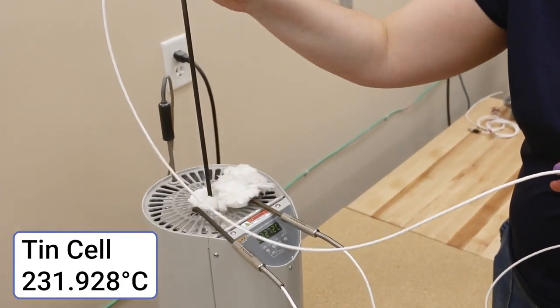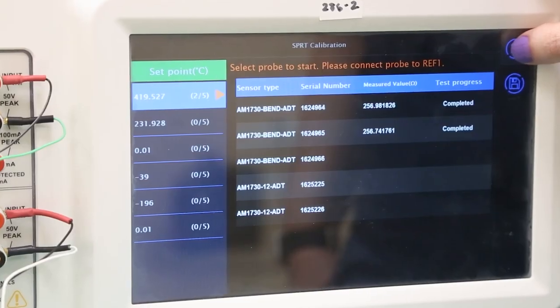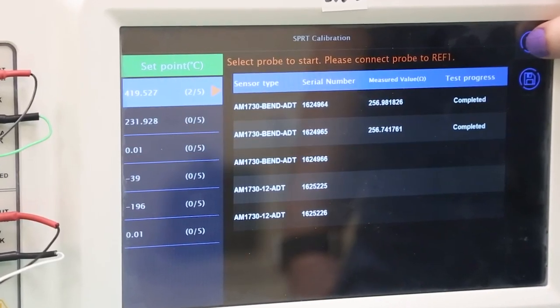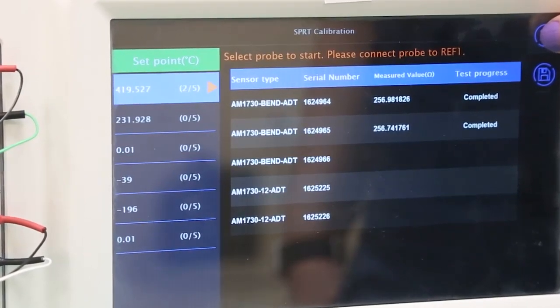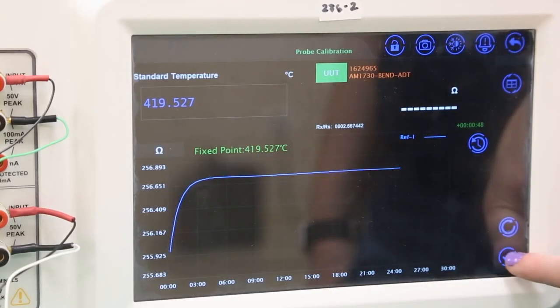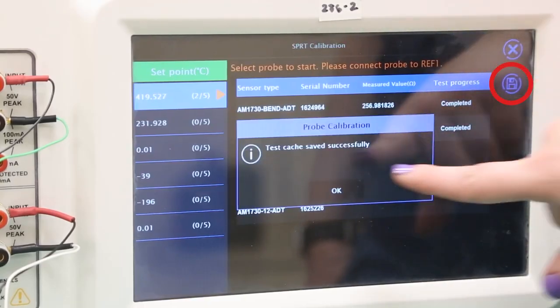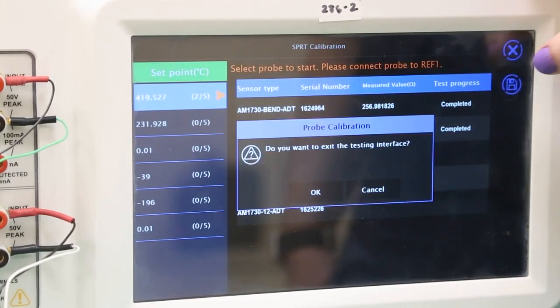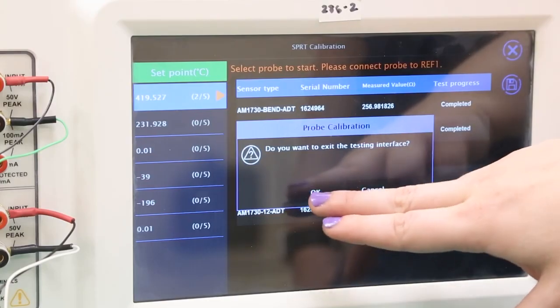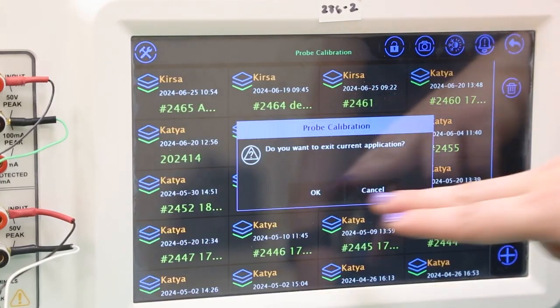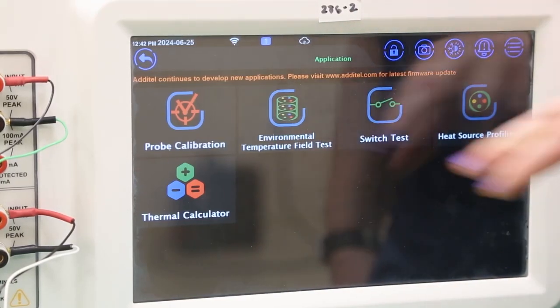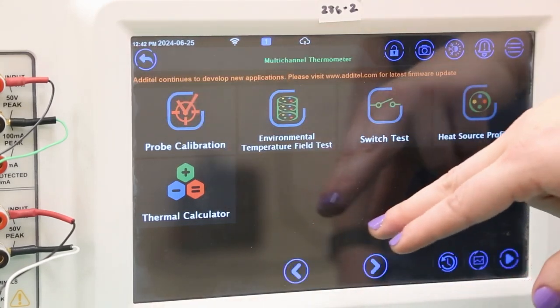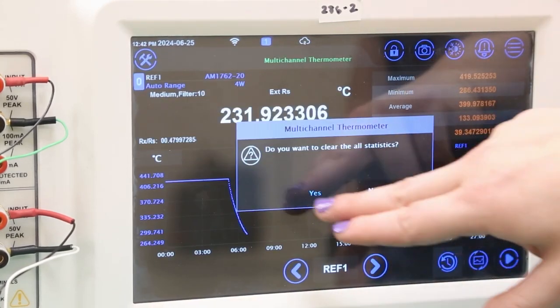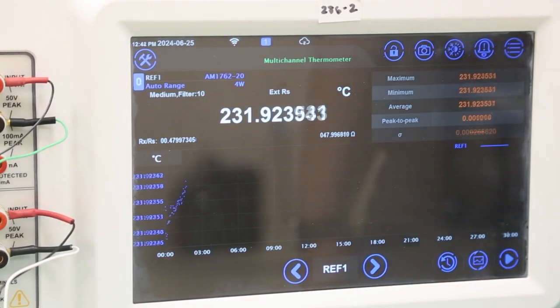One of the advantages of the fixed point program on the 286 is that any probe can be measured at any calibration point in any order. To do this, first save the test cache on the current calibration by pressing the Save icon. You can now close the test and return to the multi-channel thermometer application. After inserting the reference thermometer into the tin cell, repeat the process of waiting for the temperature to stabilize by clearing statistics and checking the average and peak-to-peak values shown on the 286.